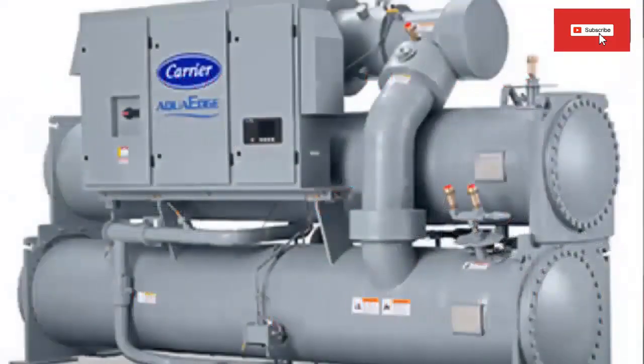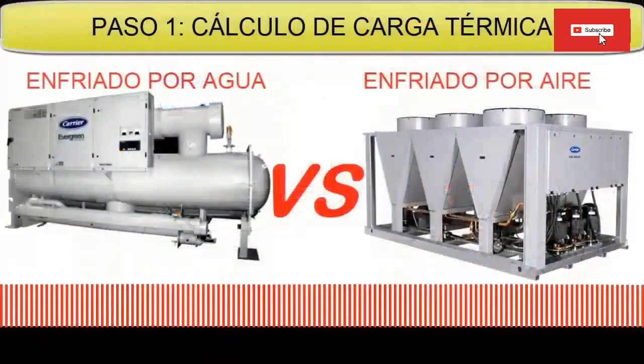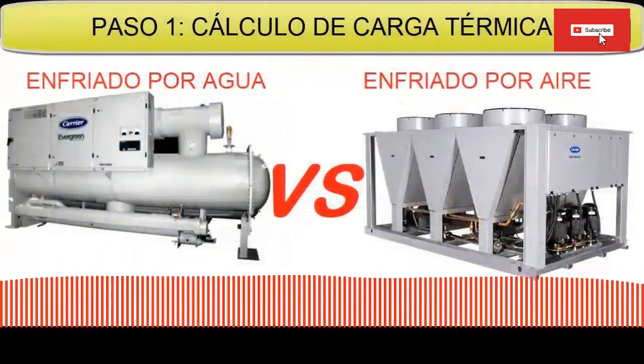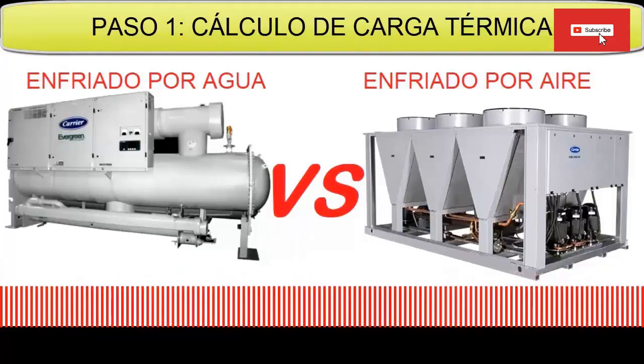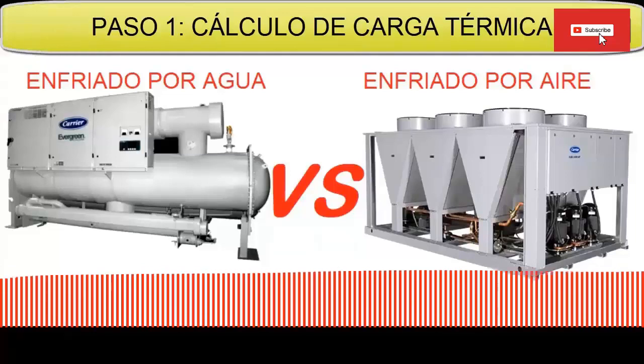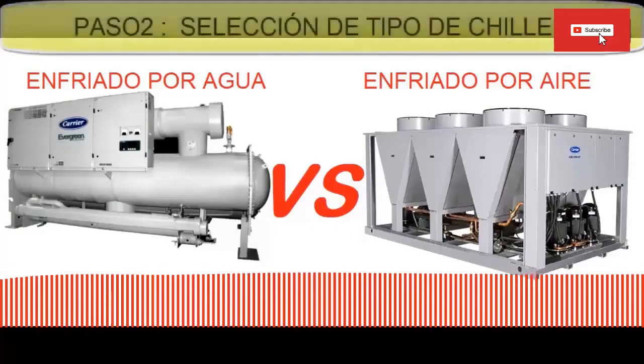The first step for the selection of a chiller is the calculation of the thermal capacity that it must have. By the way, the procedure to calculate a chiller was analyzed in our previous video. The link is appearing above, if you want to take a look. Once the capacity has been calculated, we must focus on the type of machine that best suits the needs of the installation.